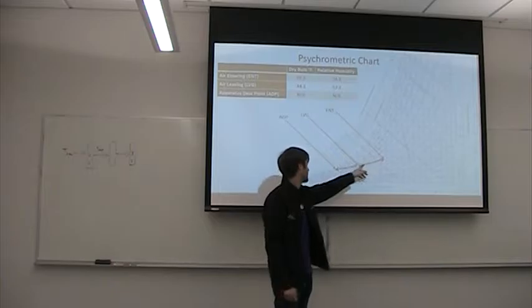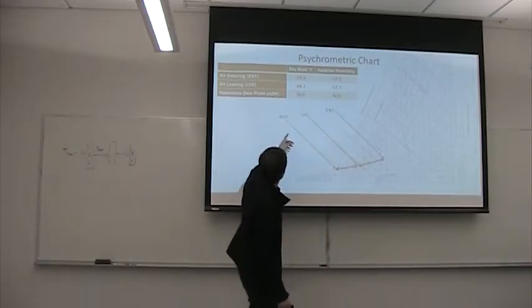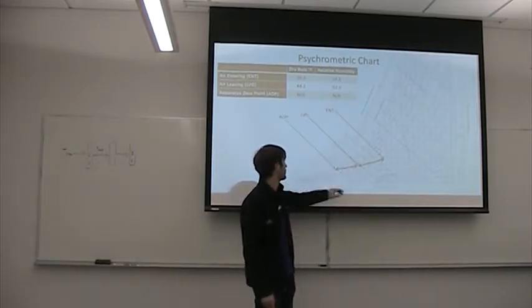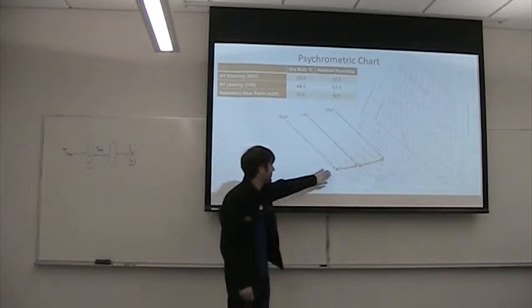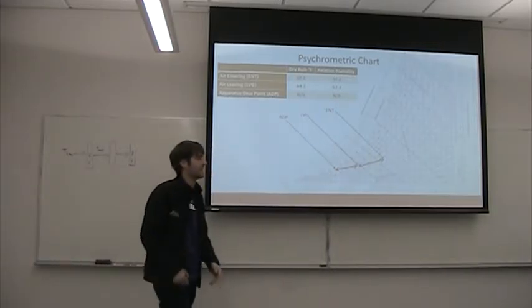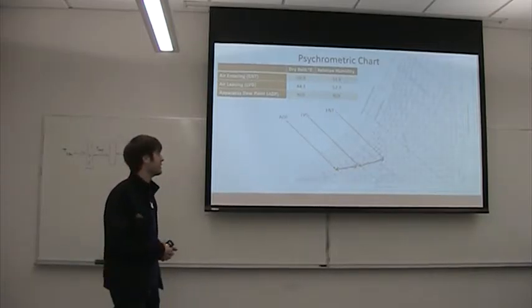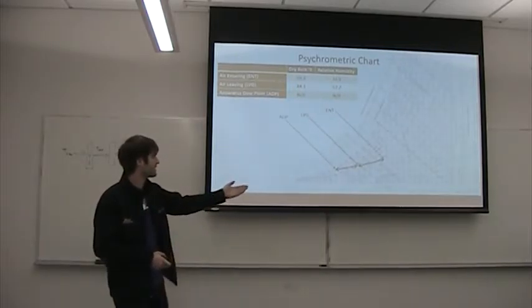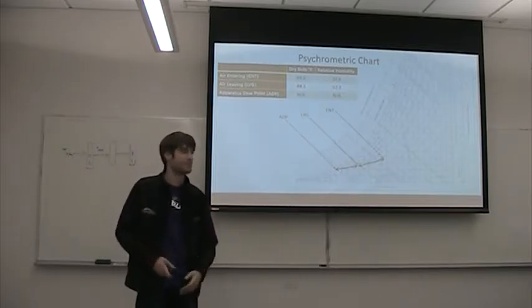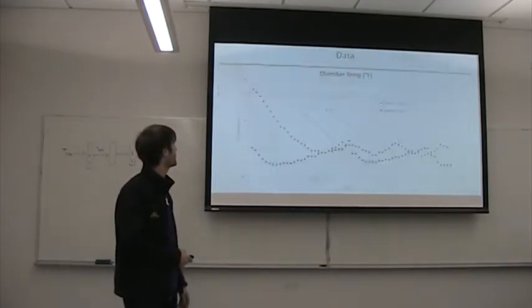And then this is the psychrometric chart. So for this you can estimate your apparatus dew point. You graph your air entering the system. And then the plot of the point of the air leaving the system with the dry bulb temperatures and your relative humidities. And then with the straight line you can estimate your apparatus dew point here on the chart.